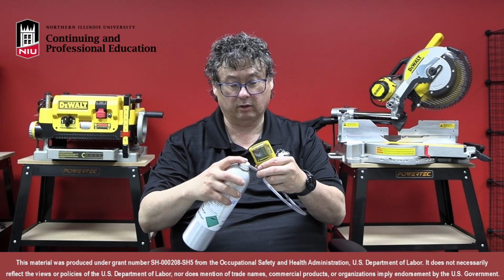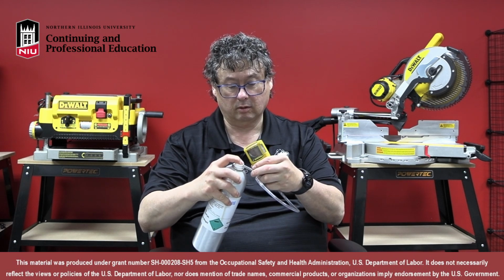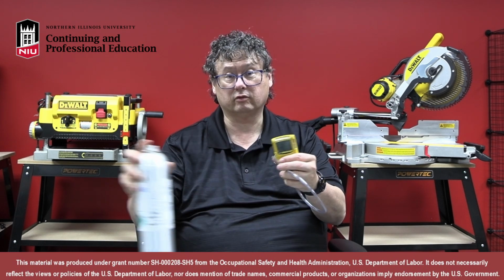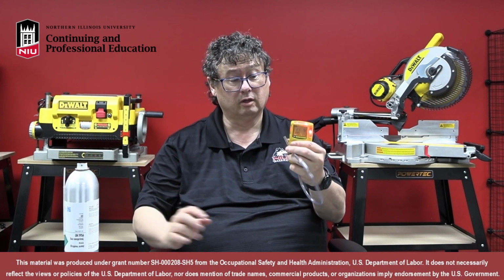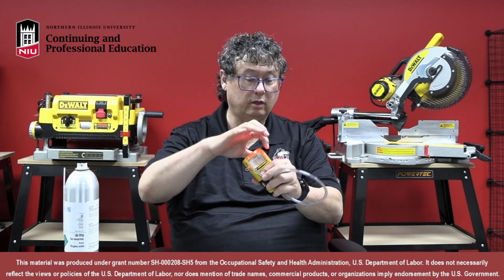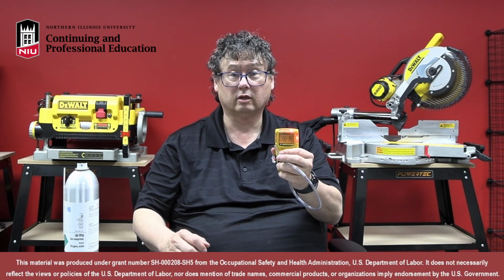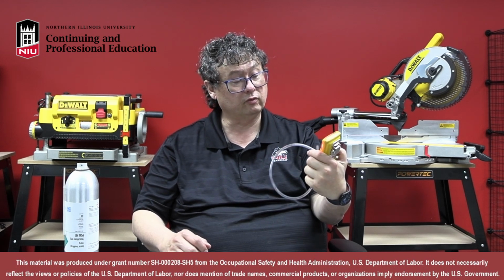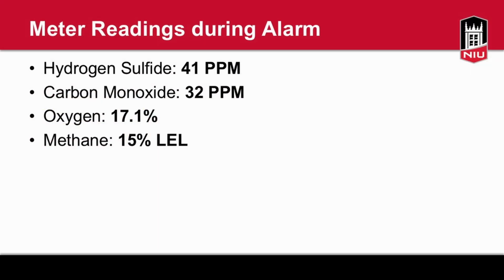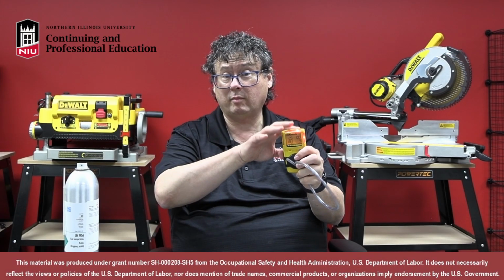And if I just spray it in here, just a little gas, you're not getting much in it. We notice 1, 2, 3, 4 sensors are working. And if I just read some numbers, it's at 41 hydrogen sulfide, 132 carbon monoxide, 17.1 oxygen, and 15% LEL, just in a gas. You want to make sure.